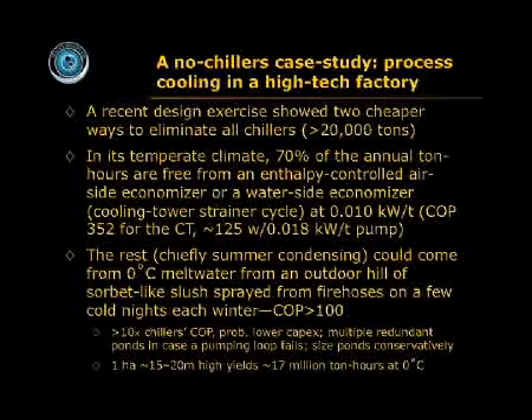It was in a temperate climate, hot in the summer, cold in the winter. And it turned out, by going carefully through the psychrometric charts, we could get 70% of the annual ton hours for free from airside and waterside economizers. And the COP was 352 for the cooling tower and about 125 for the system, because you have to count the chilled water pump. Still not bad.